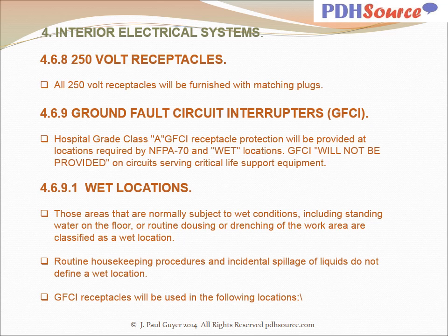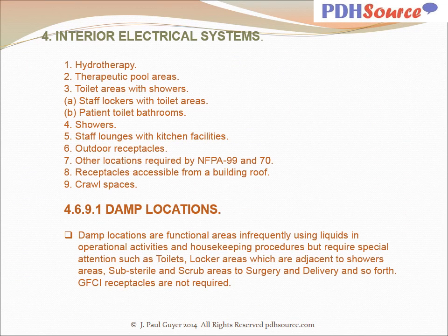GFCI receptacles will be used in the following locations. Hydrotherapy, therapeutic pool areas, toilet areas with showers, staff lockers with toilet areas, patient toilet bathrooms, showers, staff lounges with kitchen facilities, outdoor receptacles, other locations required by NFPA 99 and 70, receptacles accessible from a roof, building roof, crawl spaces. Damp locations are functional areas infrequently using liquids in operational activities and housekeeping procedures, but require special attention, such as toilets, locker areas, which are adjacent to shower areas, sub-sterile and scrub areas to surgery and delivery, and so forth. GFCI receptacles are not required.